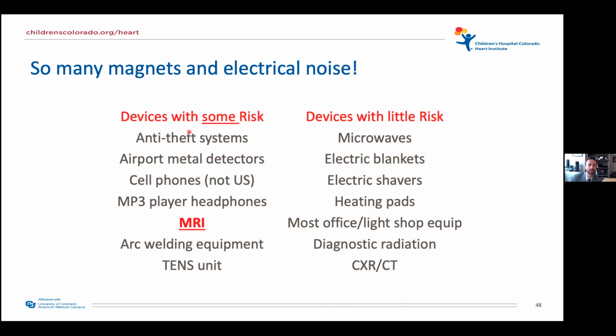However, there are some things that have some risk and need to be understood. The things that a lot of people bring up are airport metal detectors, cell phones, and MP3 players. Airport metal detectors do have magnets, but walking through one has essentially no risk. Having one of those wands moved over the device will set off the metal detector, but just moving it over the device is not dangerous. You politely inform security, please don't hold it over my device, but that is not something that needs to be reprogrammed or anything.